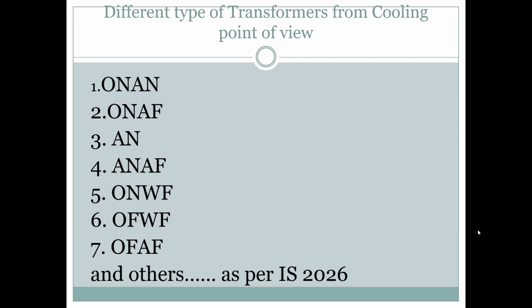Now next-generation transformers are coming where we don't need oil. This is being tried out, and up to a certain MVA rating it is very successful. Where hazardous areas are there, where oil catches fire, we have removed the oil, and that is air natural, the dry type transformer. There is no oil, and they also use fans for cooling. Then oil natural, water forced: in some special uses of transformers, water pumps are there to cool the transformer. OFWF, oil forced, water forced: oil is also pumped and water is also pumped. These are the nomenclatures given in the standards, and OFAF is oil forced, air forced. These are all as per the standard, which is the mother specification for oil filled transformers.